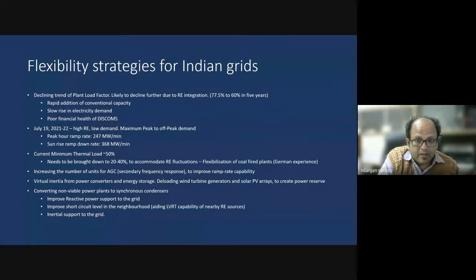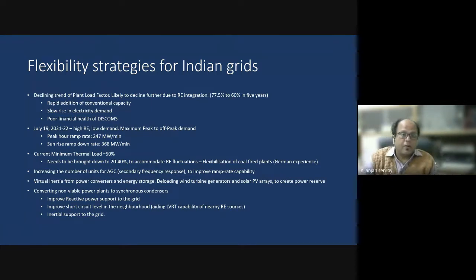Then there is extensive use of synchronous condensers in order to improve the reactive power support to the grid, improve the short circuit level in the neighborhood, and finally provide inertial support to the grid. So we need to have a lot of rotating machines and not just STATCOMs and SVCs, which can provide both reactive power and inertial support.